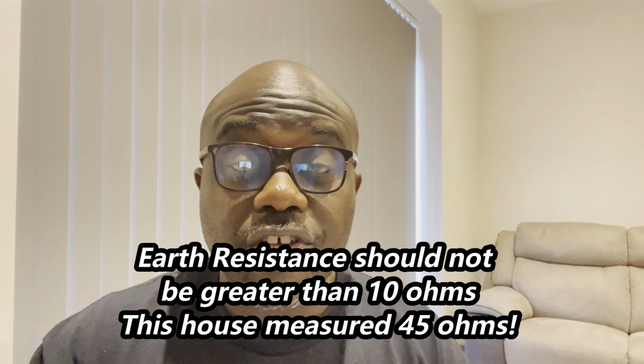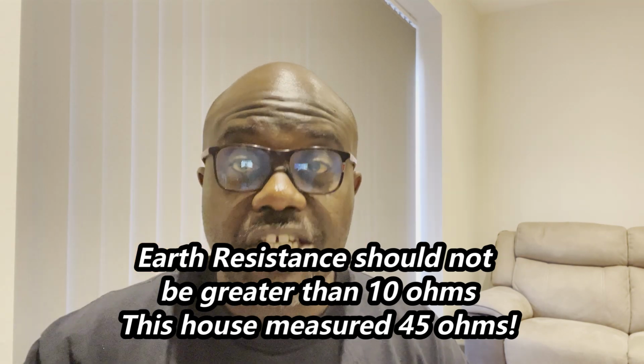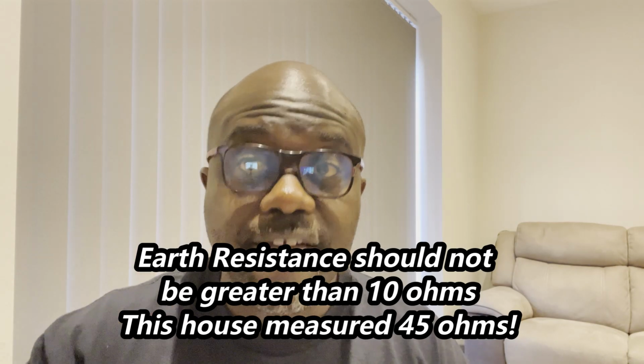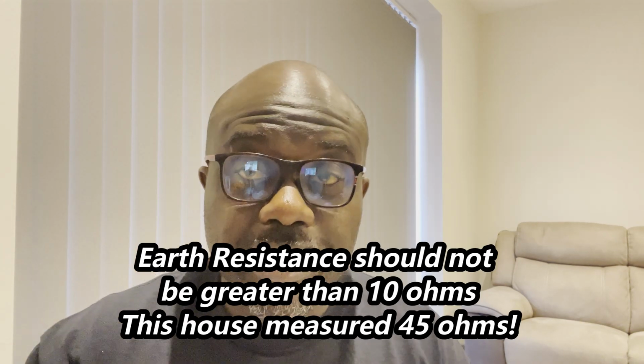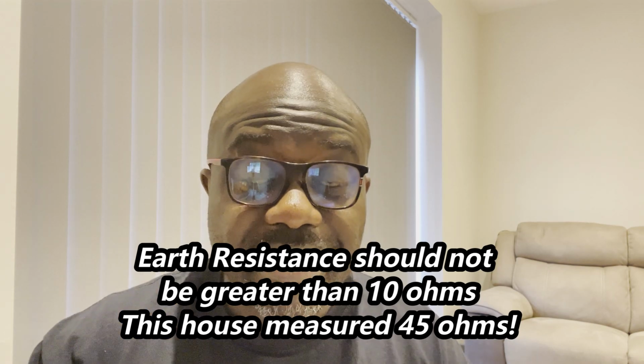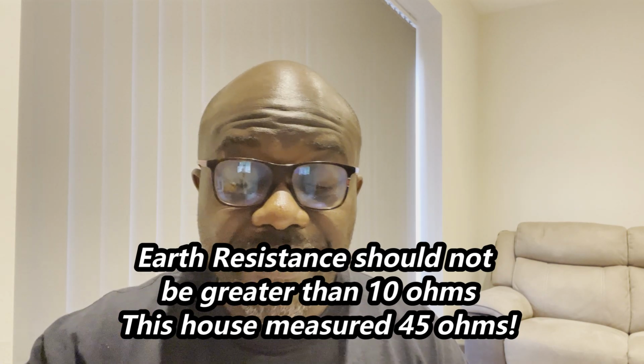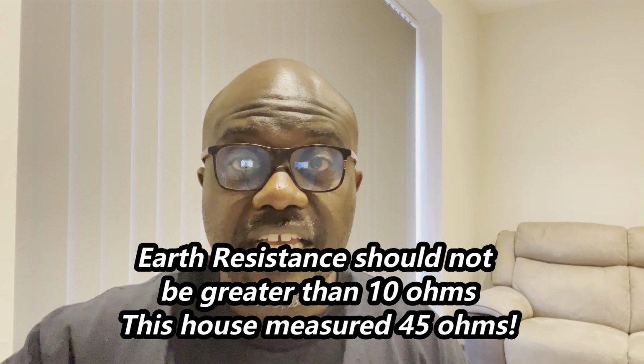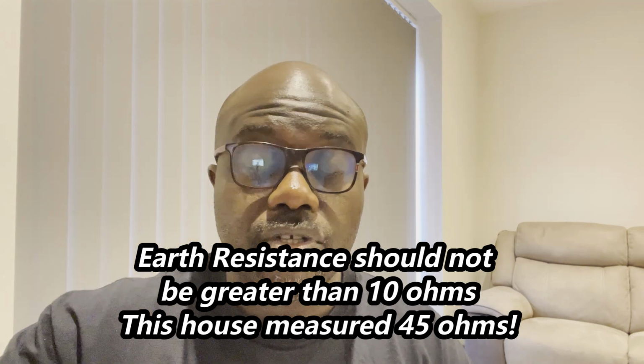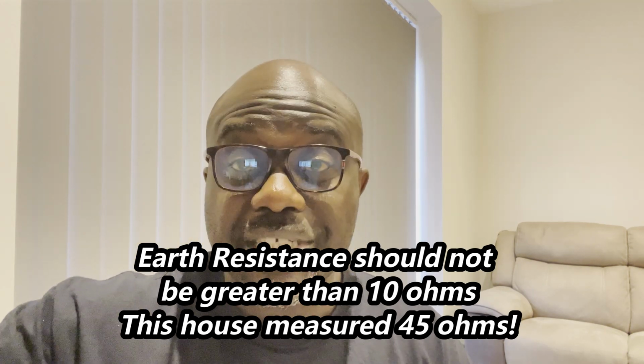Unfortunately, on this client's home, the resistance to earth when measured was 45 ohms. Okay, 45 ohms, which makes this situation even worse. At such high resistance, it means if there was an earth fault or an electric issue in his home and somebody was getting electrocuted, by the way, there's no RCCB, it could be definitely fatal because the earthing installation is non-compliant. The impedance is too high. So again, we had to resolve that issue.